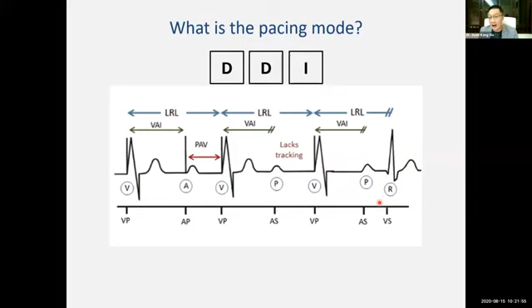Third alphabet means what is the response to sensing? Now, look very closely here. The P wave here has been sensed, but it does not initiate an AV interval. So it means that at the atrial level it has been inhibited rather than triggered. At the ventricular level, we know that it's been inhibited. So the third alphabet should be an I. So it's DDI mode. Now let's talk about these four modes of DDD pacing.